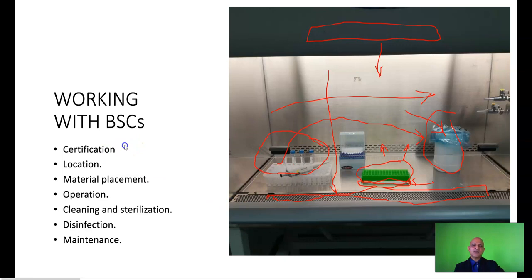Okay, these are some points which you must note. First, your facility must be certified periodically by a specific service provider. So there's a certification procedure. The facility should be located away from drafts of air. There should be no air circulation near the biological safety cabinet. The placement of your material I have discussed here in this particular photograph. The operation should be in accordance with standard operating procedures.